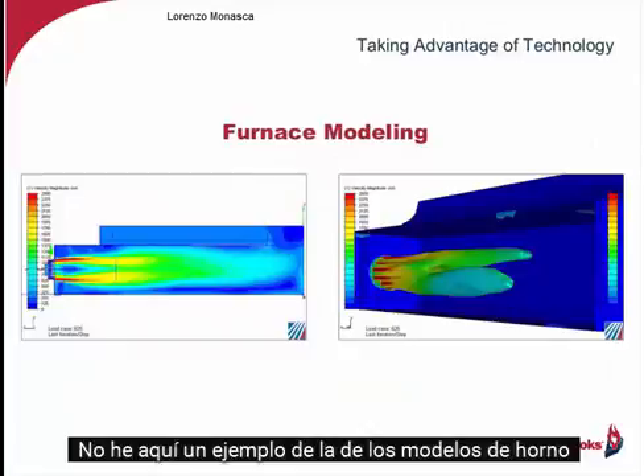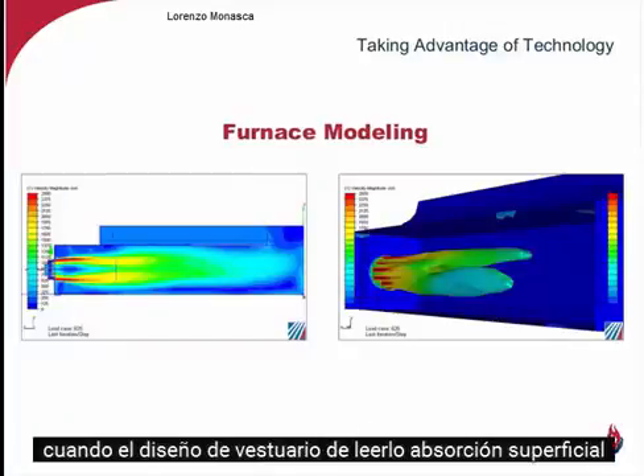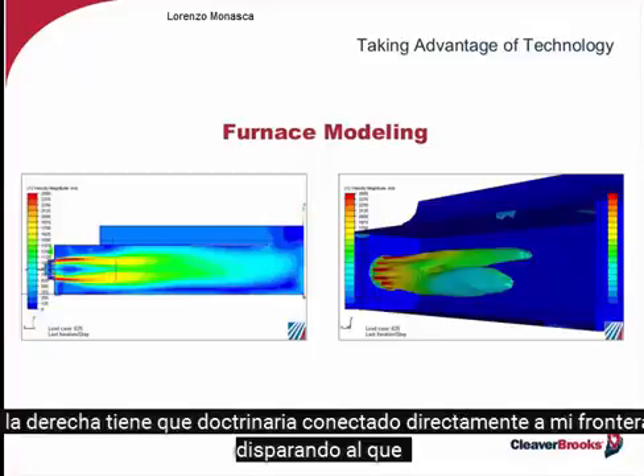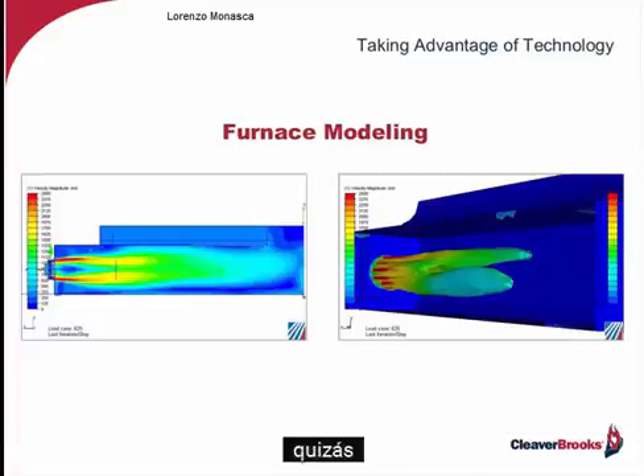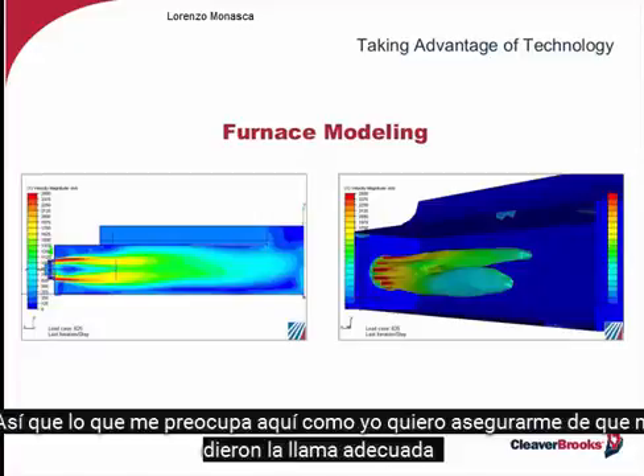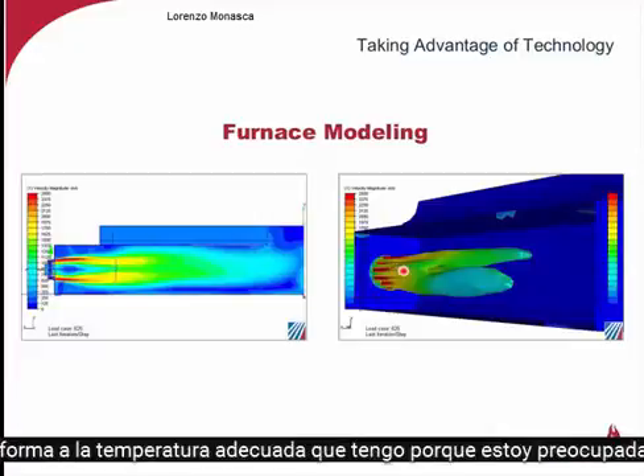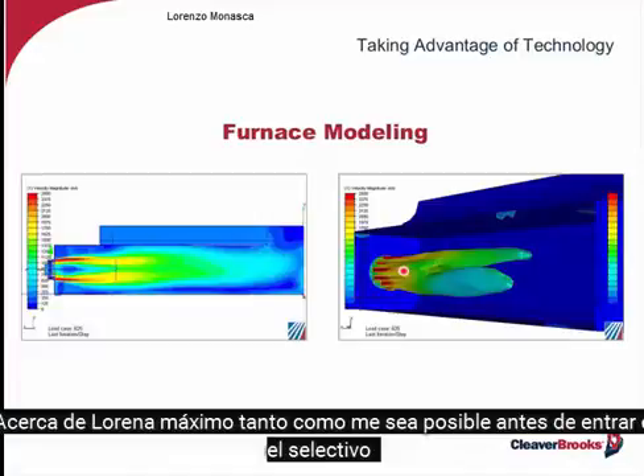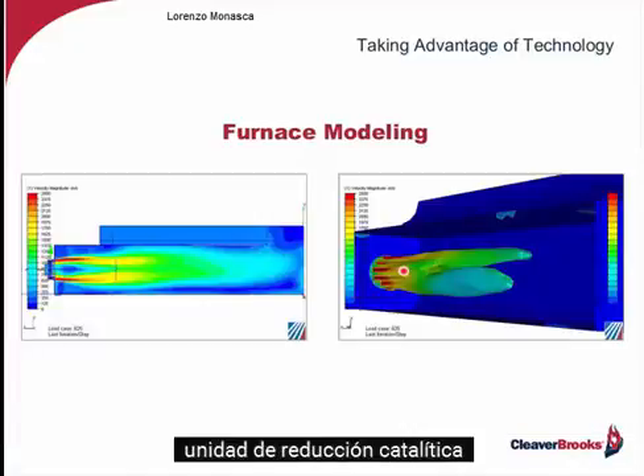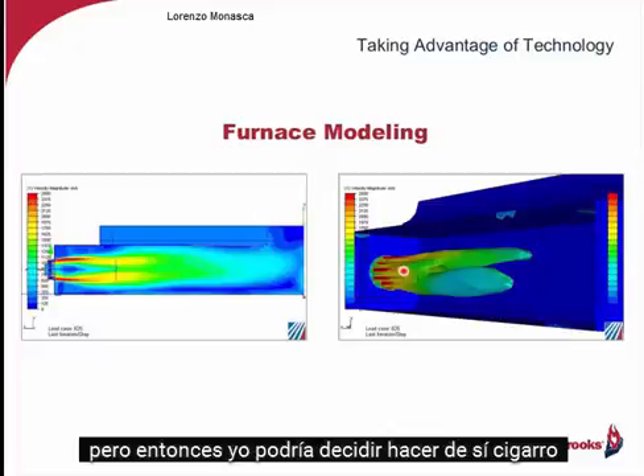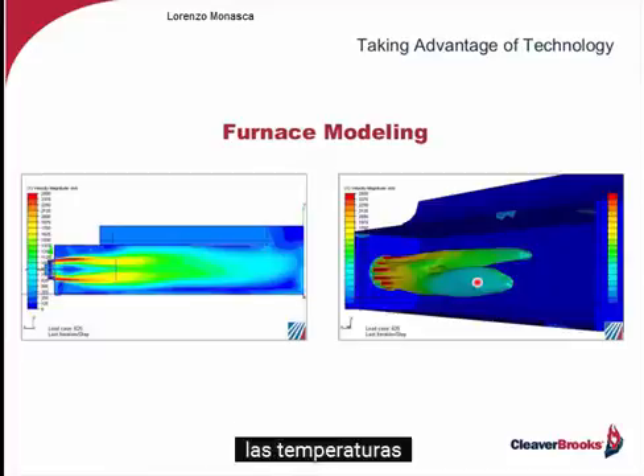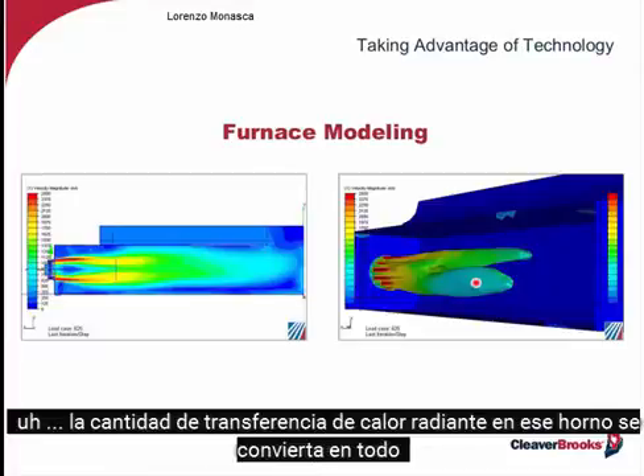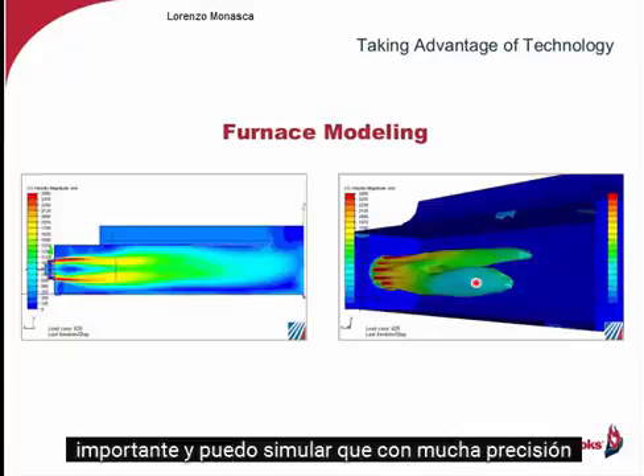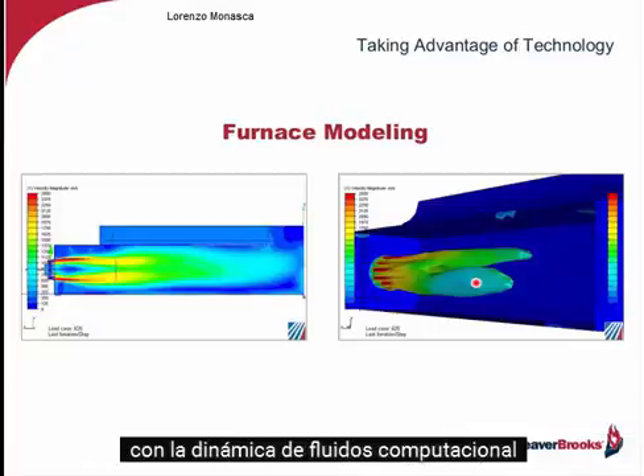Now, here's an example of the furnace modeling when the design calls for radiant surface absorption, where I've got that duct burner connected directly to my boiler, firing into that furnace. So what I'm concerned about here is I want to make sure I've got proper flame shape, I've got proper temperature, because I'm concerned about lowering the NOx as much as I possibly can before I go into the selective catalytic reduction unit to minimize the size of the SCR and limit the amount of cost associated with it. So the flame pattern, the temperatures, the amount of radiant heat transfer in that furnace become all important, and I can simulate that very accurately with computational fluid dynamics.